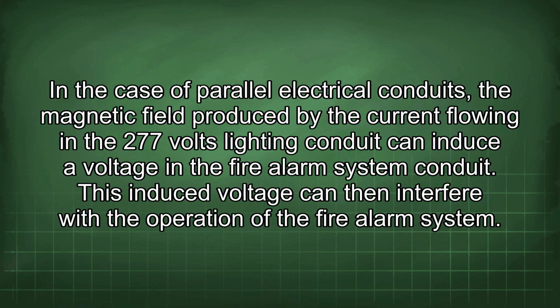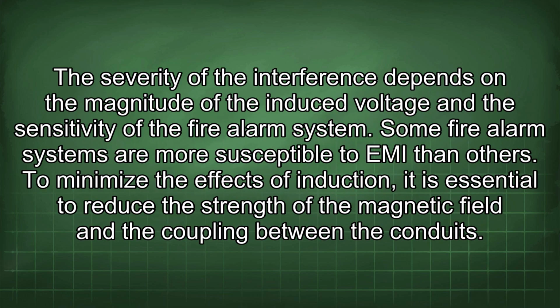In the case of parallel electrical conduits, the magnetic field produced by the current flowing in the 277 volts lighting conduit can induce a voltage in the fire alarm system conduit. This induced voltage can then interfere with the operation of the fire alarm system. The severity of the interference depends on the magnitude of the induced voltage and the sensitivity of the fire alarm system. Some fire alarm systems are more susceptible to EMI than others.